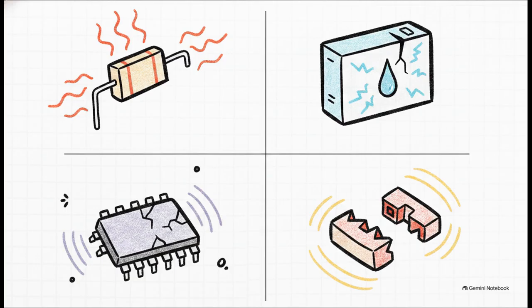First up is thermal drift. You've got these mega-ohm precision metal film resistors measuring up to 1,000 volts, sitting dangerously close to heat-generating modules. Over time, that intense heat actually causes metal atoms to migrate and oxidize, which permanently shifts their resistance and distorts the voltage reading. Second, if the battery box loses its airtight seal, even a tiny bit of moisture ingress creates parallel resistance pathways, dragging the measured voltage abnormally low. Third, we have optocoupler aging. The high-voltage isolation circuits suffer nonlinear aging under that high heat, meaning they literally lose their signal conversion efficiency. And finally, connector fretting.